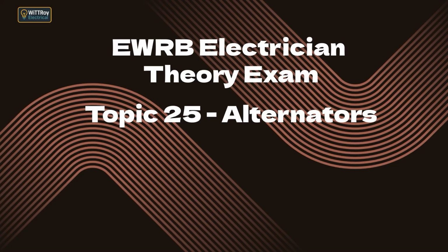Topic 25a. Explain the basic construction of an alternator. An alternator is built around three essential parts. 1. A magnetic field. This field can be produced by permanent magnets, but in large alternators it is produced by DC field windings. 2. A conductor, armature windings. These windings are arranged so that they cut through the magnetic field. 3. Relative motion. Voltage is only induced when the magnetic field and the conductor move relative to each other.